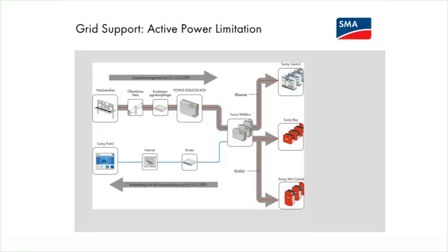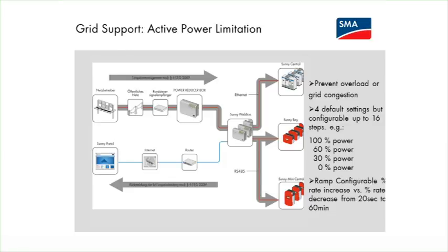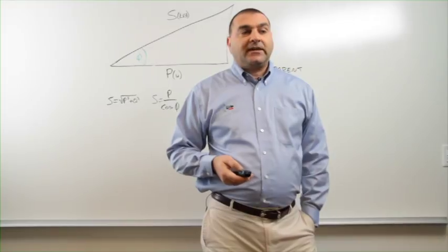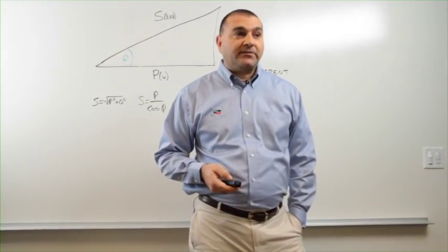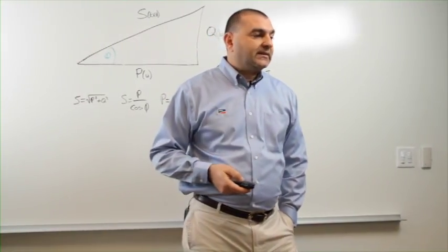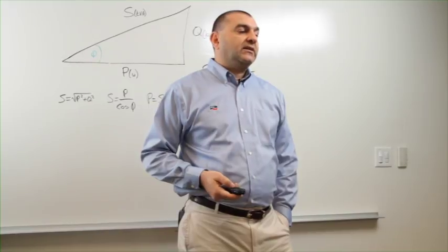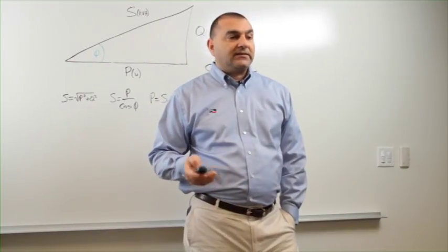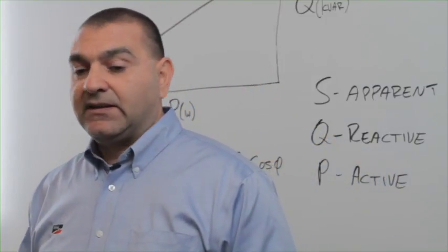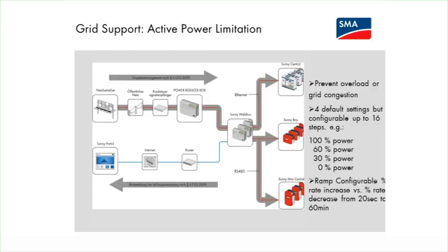Through our technology, you are able to dispatch the inverter at various power levels, usually 100% of power, 60% of power, 30% of power, or a standby 0%. That would be basically the default. But one can set 16 different settings to be able to change the power. And usually you try to do this to avoid sometimes grid congestion. A perfect example is the ERCOT market. It's understood there's some congestion sometimes, especially because of the wind that exists on the west side of the state. And ERCOT likes to have control over any sizable power plants in its market system and be able to dispatch that at different power levels. You're also able to control the ramp of the inverter, the up ramp versus the down ramp, and it's configurable between 20 seconds and basically 60 minutes.